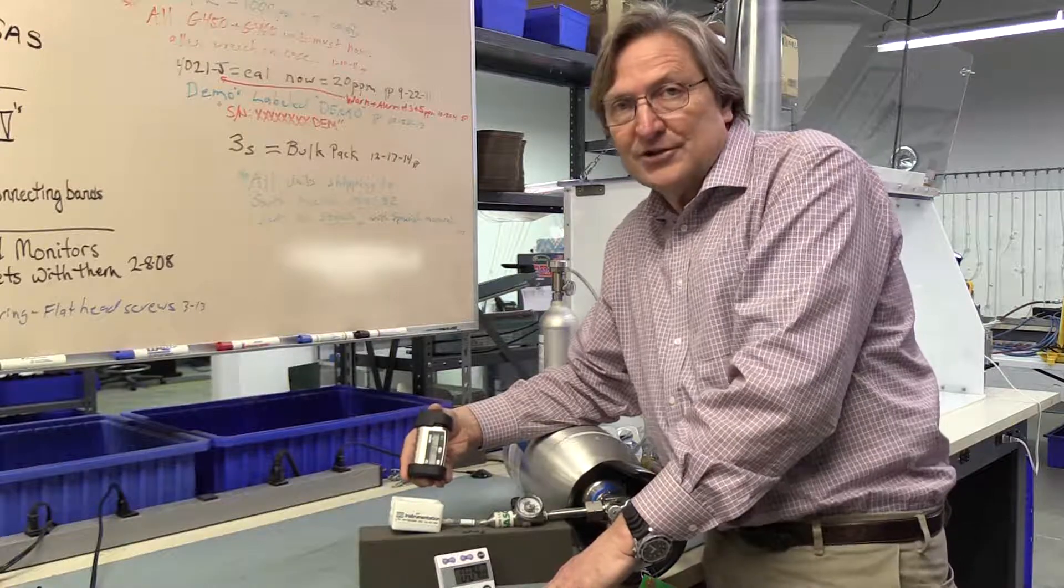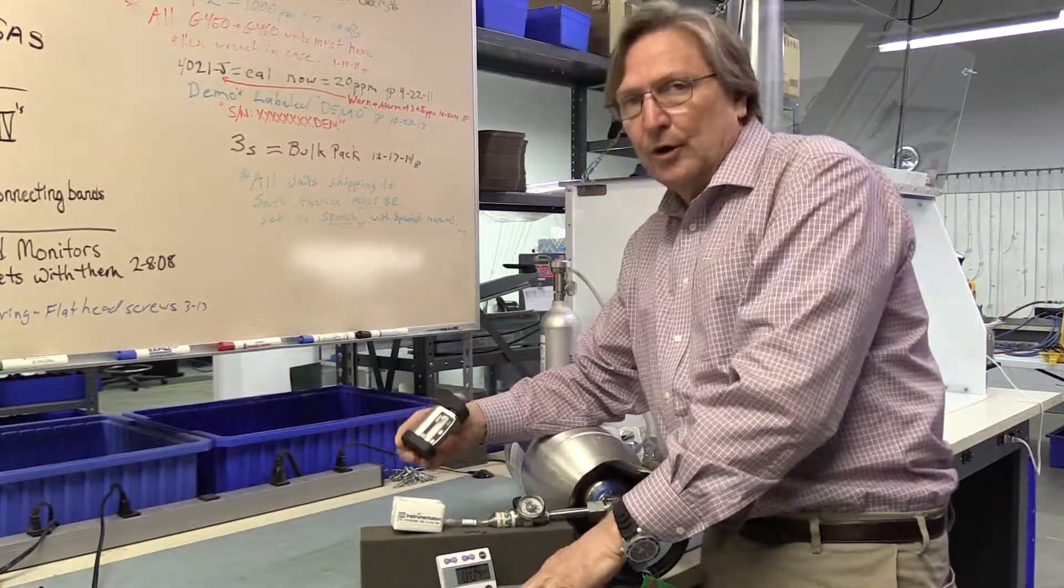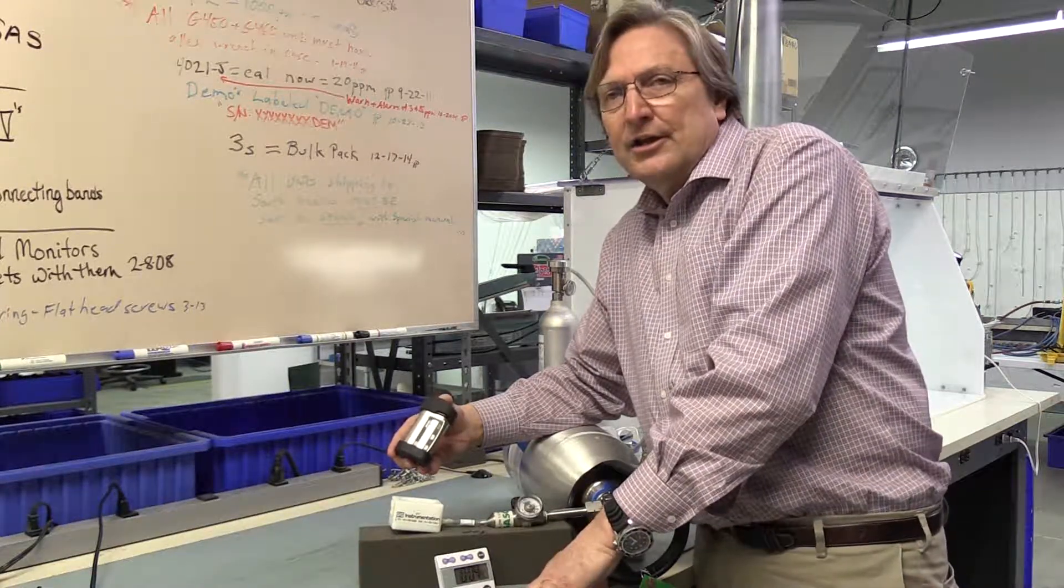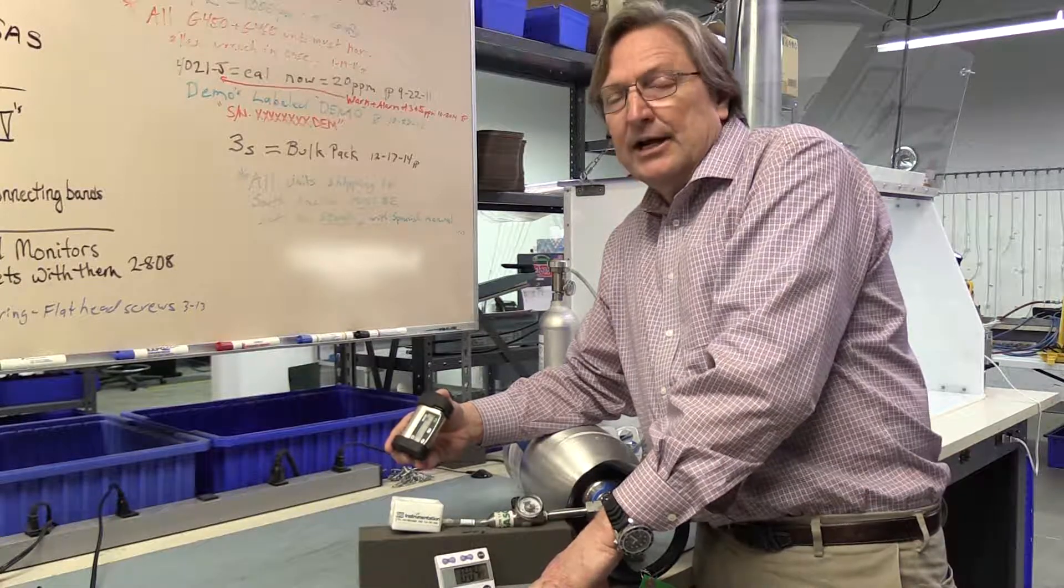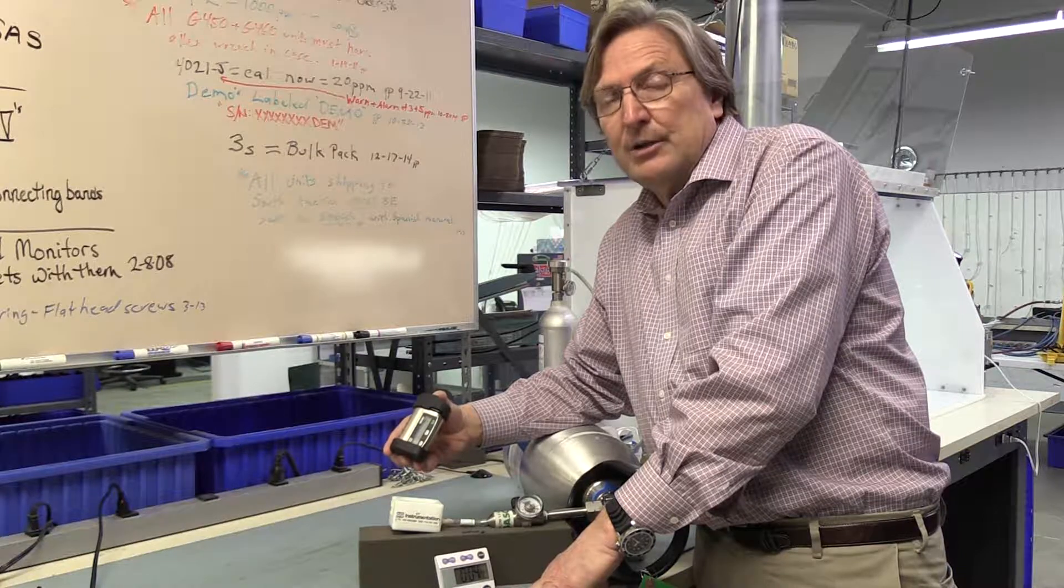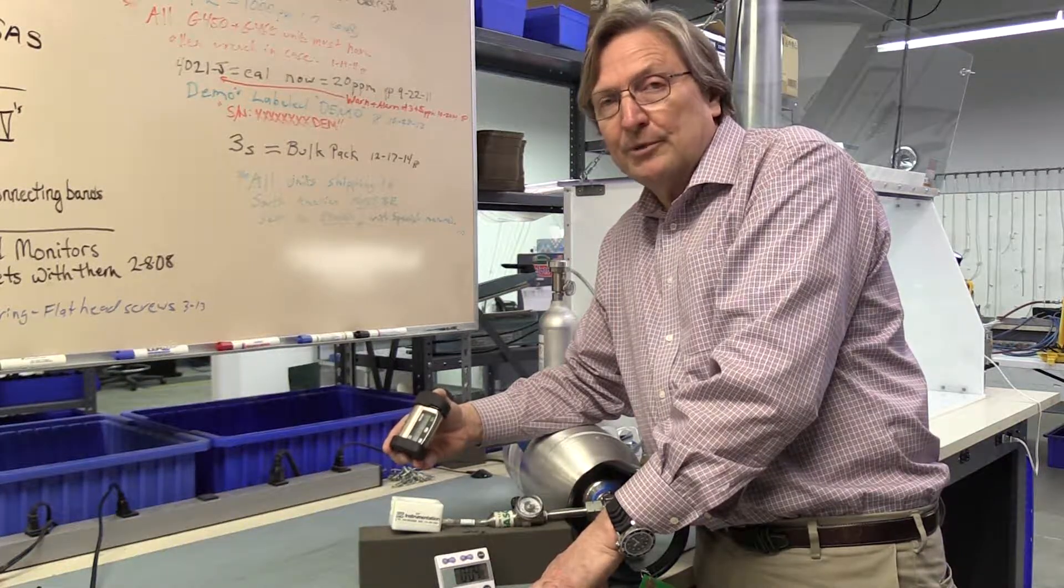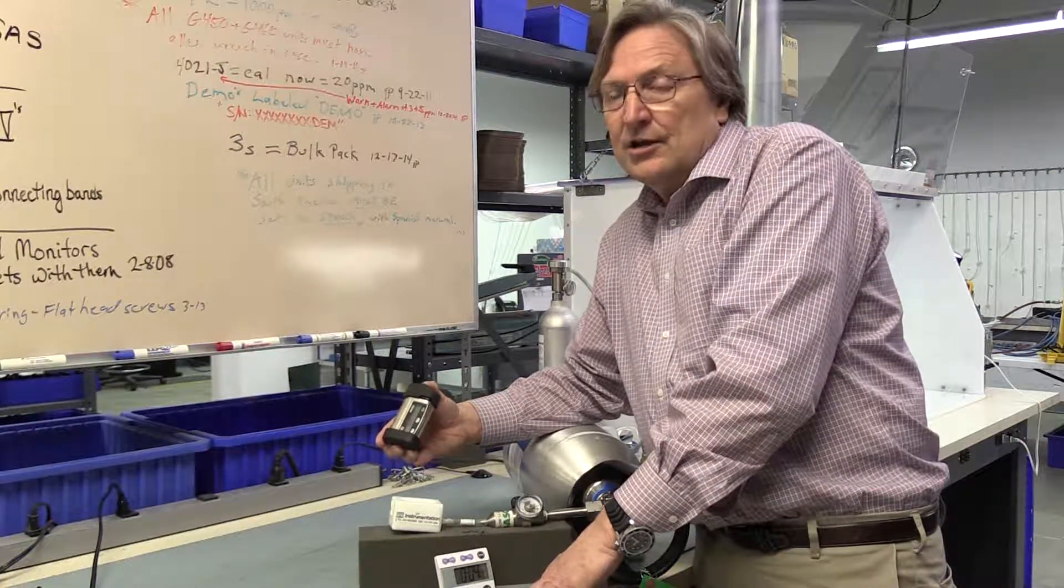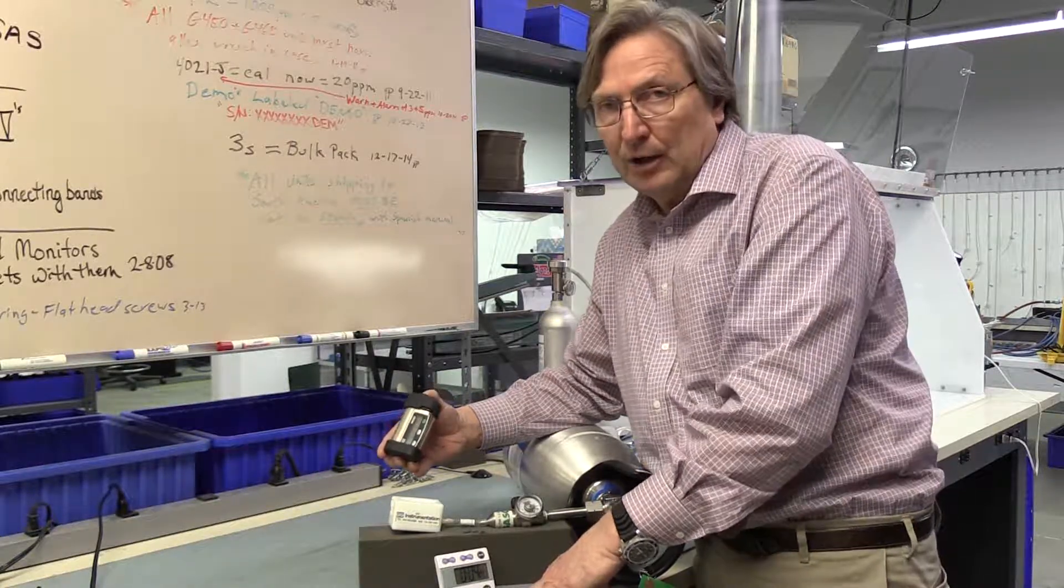The first thing you'll want to do is turn the instrument on. Now normally, before doing a bump test or cal, I like to make sure that the instrument has had a chance to warm up completely. If I have a chance, I like to let it take a full ten minutes between turning the instrument on and when I actually perform the test or the calibration adjustment. In this case, the instrument has had a chance to warm up while it's been off-camera.